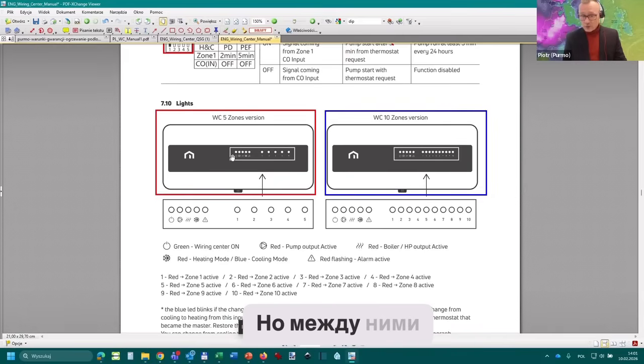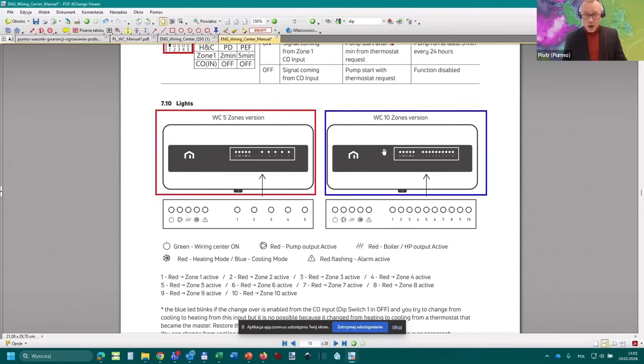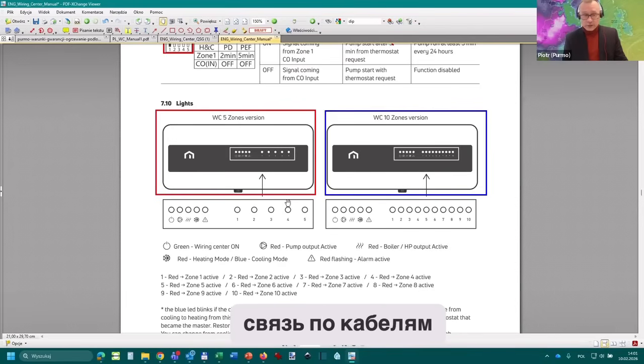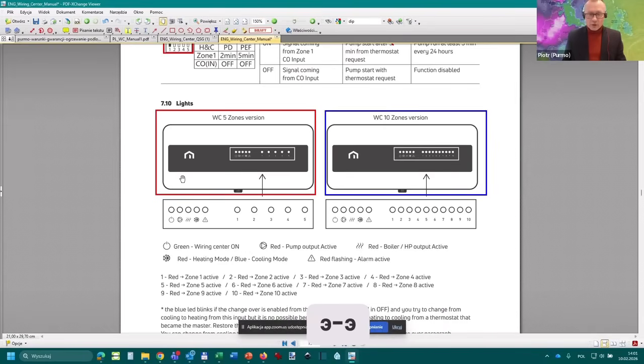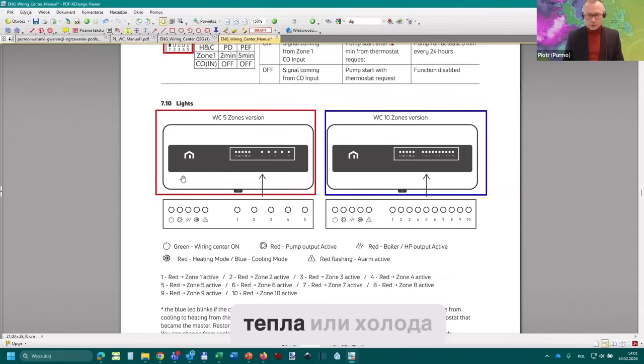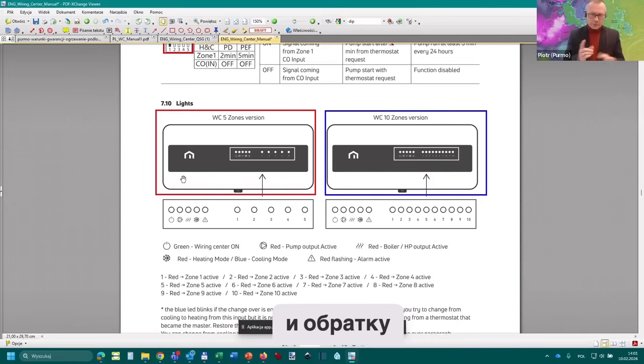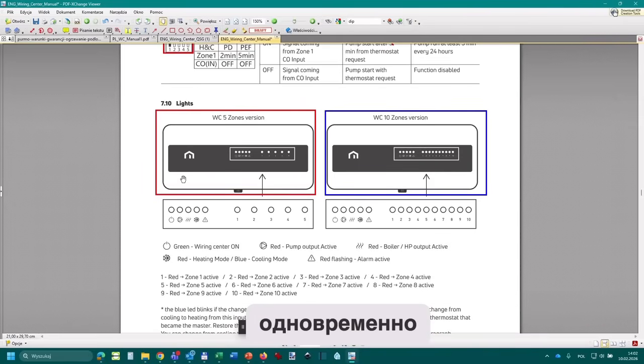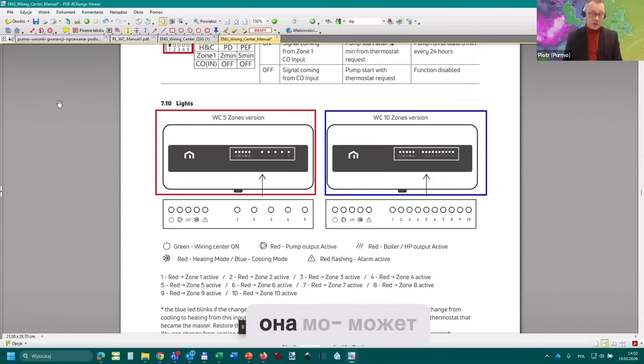But there is no communication between them, as you can see. Why? Because if you make the communication by cables, it means you manage one system, and one system cannot operate for this simple system, because the heat source or the cool source has only two pipes, input and output. So it cannot produce heat and cool at the same time. This system can control the rooms, can control the zones, but it cannot control the central system, because the source has only heating or only cooling, without the possibility to produce both, like in some fan coil systems.